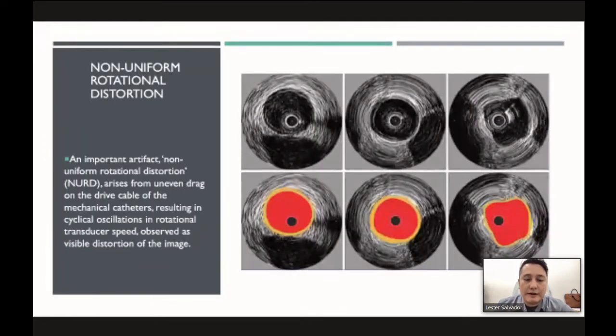Another kind of artifact you usually see is called the non-uniform rotational distortion, or NURD. It arises from an uneven drag of the drive cable of mechanical catheters, resulting in cyclical oscillations of rotational transducer speed, observed as a visible distortion of the image. NURD can occur for a number of reasons, such as the presence of acute bends in the artery, tortuous guiding catheter shape, and kinking of the imaging sheath or small guide catheter lumen. A frequent and reversible cause is excessive tightening of the hemostatic valve.